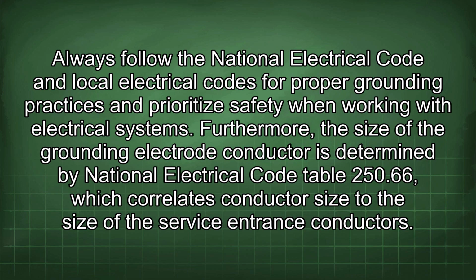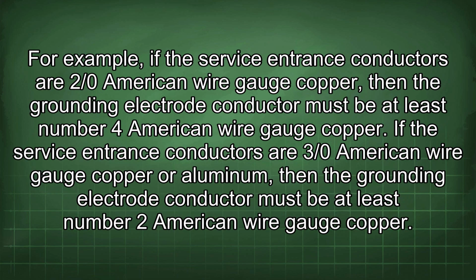electrical systems. Furthermore, the size of the grounding electrode conductor is determined by National Electrical Code Table 250.66, which correlates conductor size to the size of the service entrance conductors. For example, if the service entrance conductors are 2/0 American wire gauge copper, then the grounding electrode conductor must be at least number 4 American wire gauge copper. If the service entrance conductors are 3/0 American wire gauge copper or aluminum, then the grounding electrode conductor must be at least number 2 American wire gauge copper.